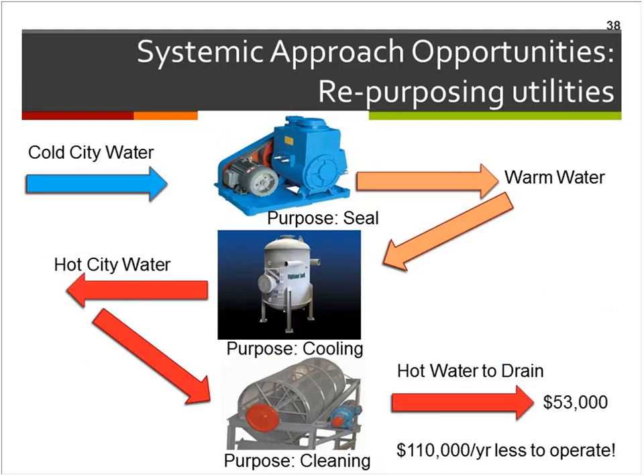What we found using a systemic approach is, let's just use the same water stream to accomplish all three tasks. By using that same water stream, you're using the heat from some tasks to provide the required heat you were previously using natural gas for. So this single stream of water now serves three pieces of equipment for three different purposes, and it's $110,000 less water use a year once you look at the system holistically.